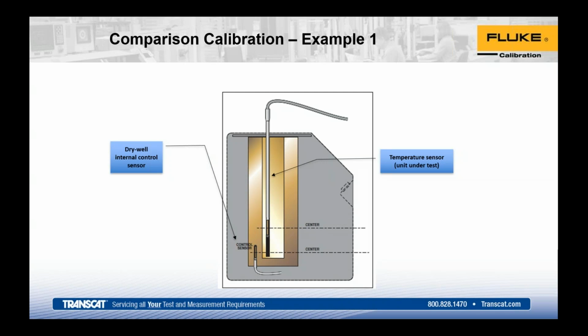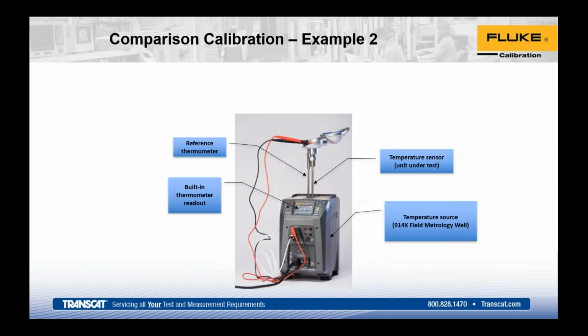So again, in this example, you can see the unit under test and the control sensor. Again, we're trying to align them very closely and then reference to the display. The next jump in a heat source and a reference, instead of calibrating just to the display, is adding a reference.